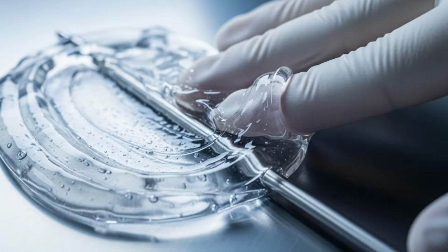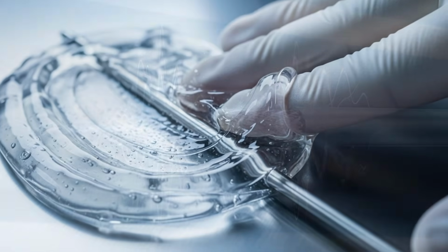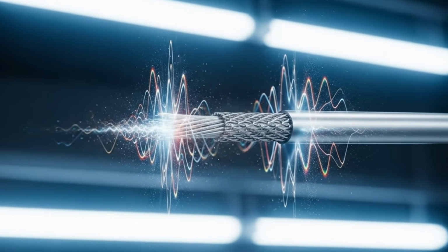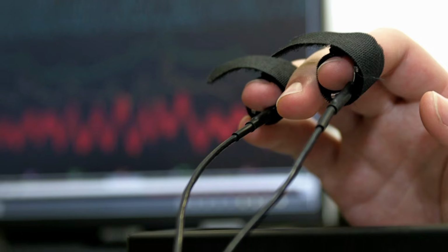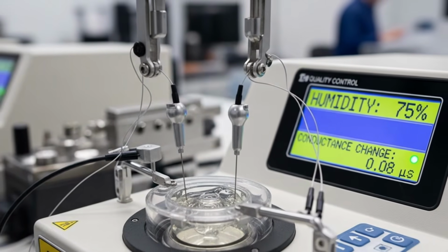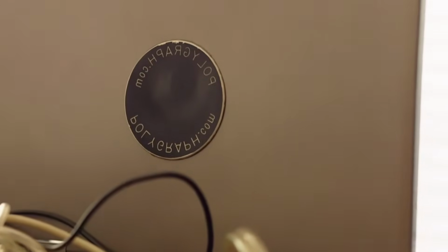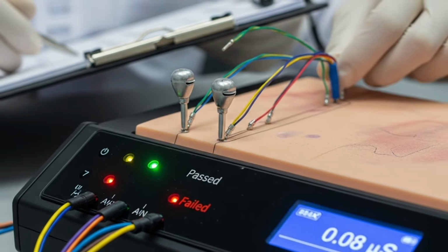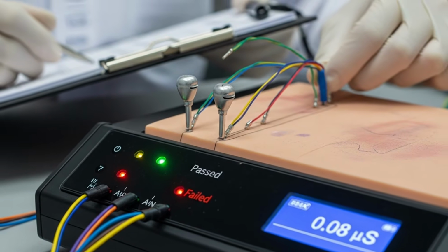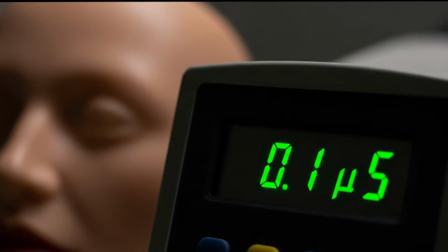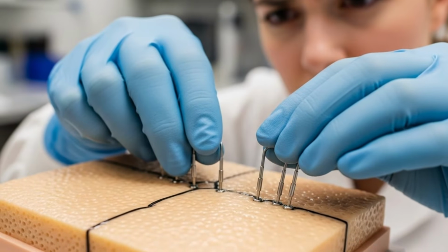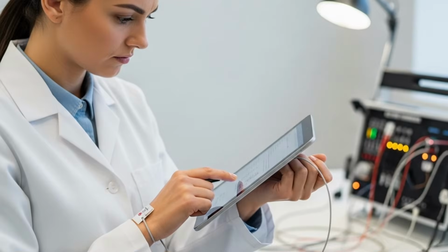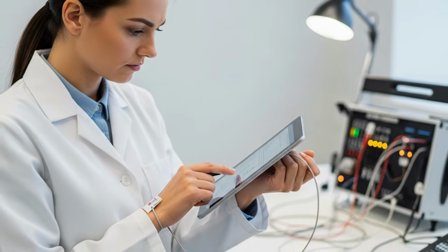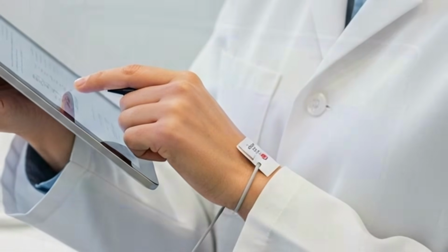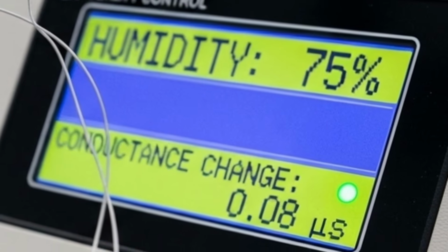The cables that connect them to the central unit are shielded to prevent electromagnetic interference from lights or nearby devices. These are soldered with automated precision equipment that controls temperature, timing, and exact bonding points to guarantee a durable, fault-free connection. Quality testing includes connecting the electrodes to simulators that reproduce the electrical properties of human skin under different humidity levels. This way, even the smallest conductance changes, as little as 0.1 microsiemens, can be verified. Only electrodes that meet this level of sensitivity move on to the next stage.